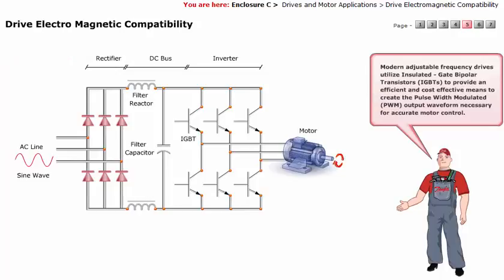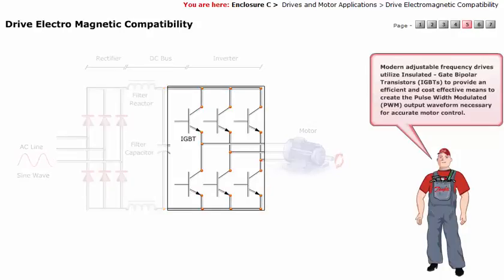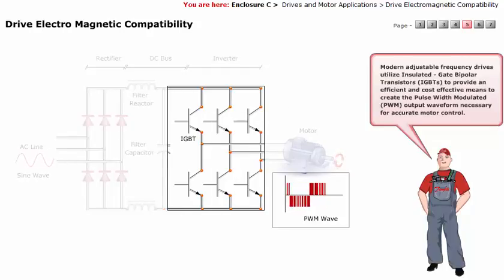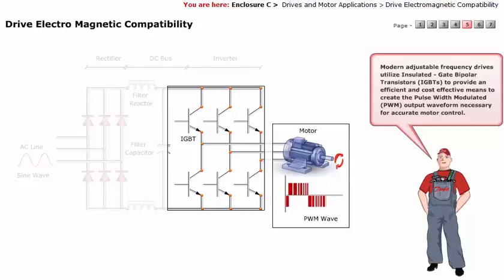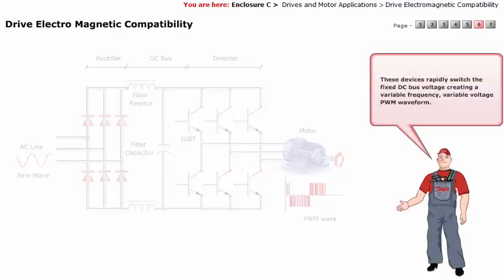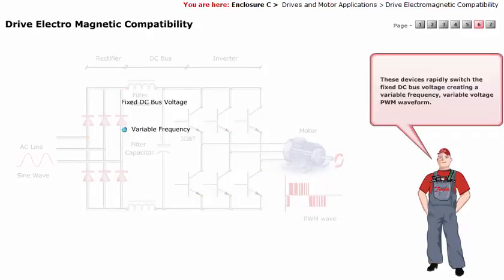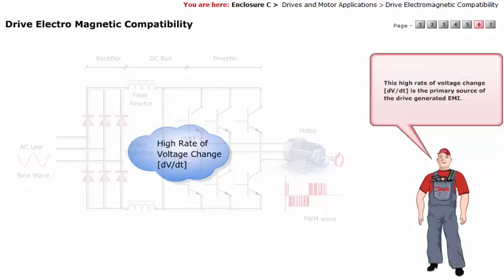Modern adjustable frequency drives utilize insulated gate bipolar transistors (IGBTs) to provide an efficient and cost-effective means to create the pulse width modulated (PWM) output waveform necessary for accurate motor control. These devices rapidly switch the fixed DC bus voltage, creating a variable frequency, variable voltage PWM waveform. This high rate of voltage change (dV/dt) is the primary source of drive-generated EMI.